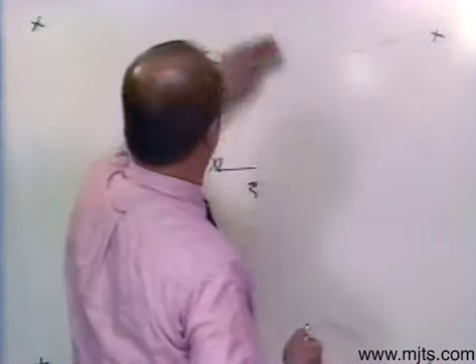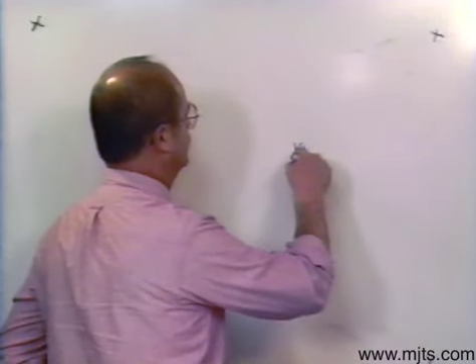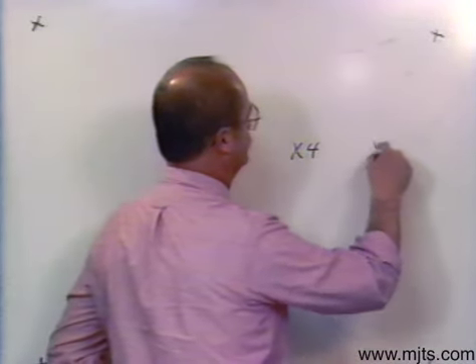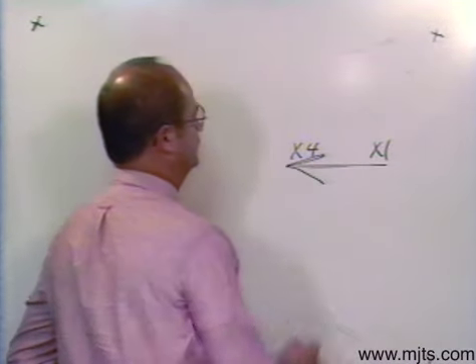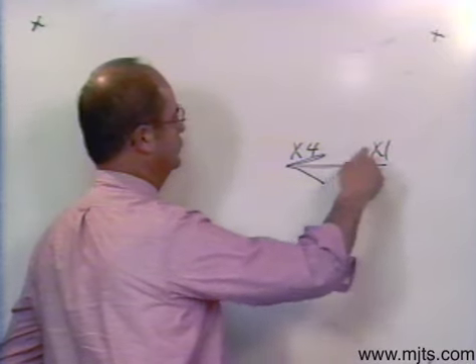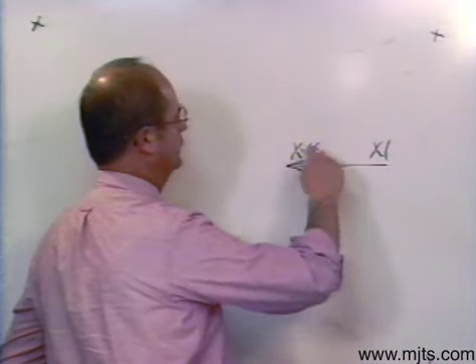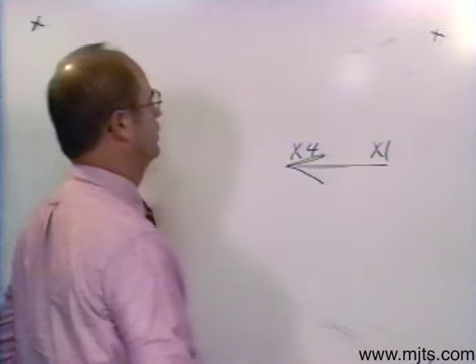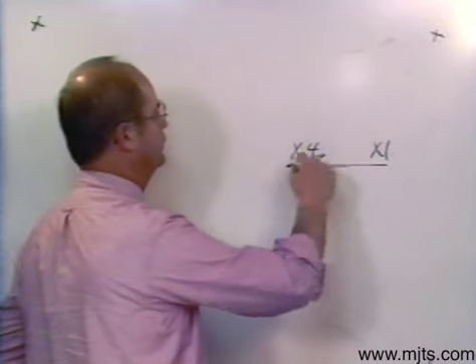On your 4-bushing transformer, you want to make sure that you're using X4 and X1 for a vector. When you parallel, it'll be X1 and X4. If you series connect, it'll still be X1 and X4, and then it all depends on what voltage value you're trying to come up with on your vector.